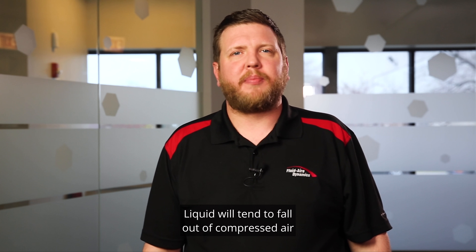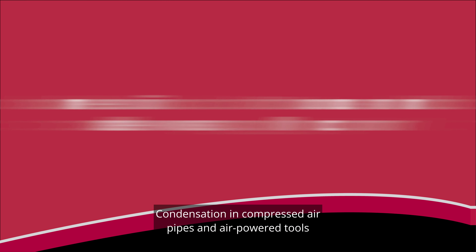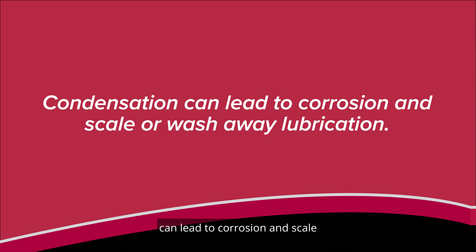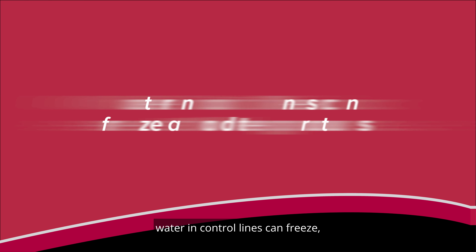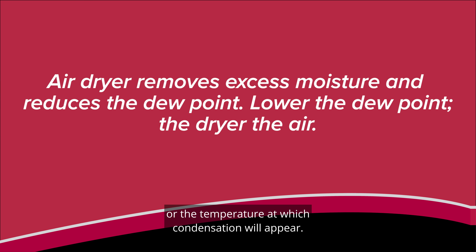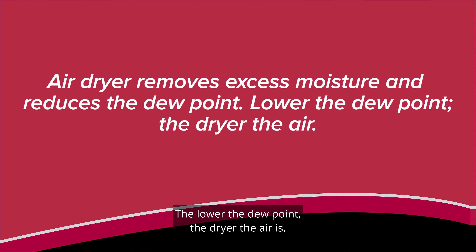Liquid will tend to fall out of compressed air as it moves through the piping system and cools. Condensation in compressed air pipes and air power tools can lead to corrosion and scale, or wash away lubrication in production equipment. If piping is exposed to cold temperatures, water and control lines can freeze, causing blockages or damaging the lines. The air dryer removes excess moisture from the air and reduces the dew point — the temperature at which condensation will appear. Dew point is often used as a measurement of moisture content in compressed air; the lower the dew point, the drier the air.